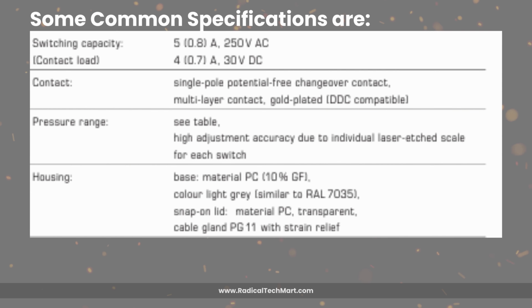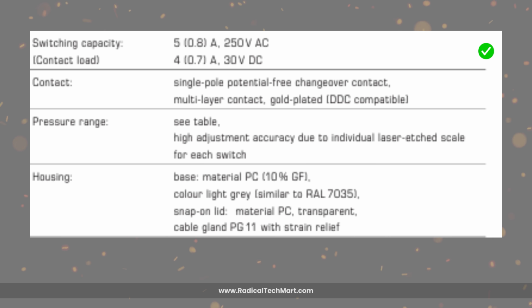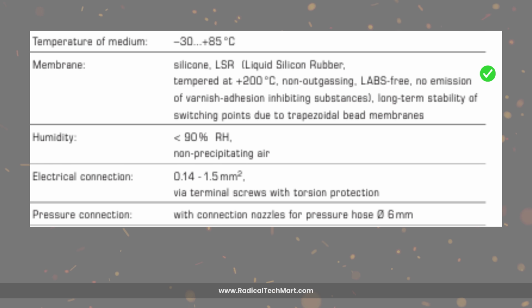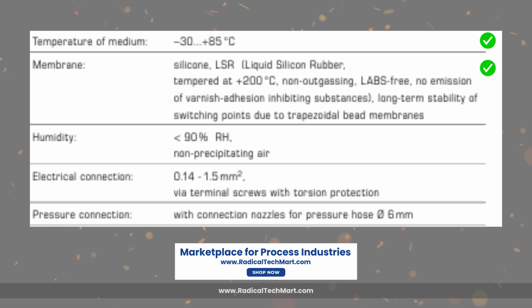Some common specifications are: 1. Switching capacity, which is around 5 into 0.8 A at 250 volts AC and 4 into 0.7 A at 30 volts DC. 2. Contact type will be SPDT, single pole, double throw, potential-free, gold-plated contacts. 3. Membrane material is LSR, liquid silicone rubber, resistant up to plus 200 degrees Celsius. 4. Temperature range of both DS1 and DS2 is minus 30 degrees Celsius to plus 85 degrees Celsius.